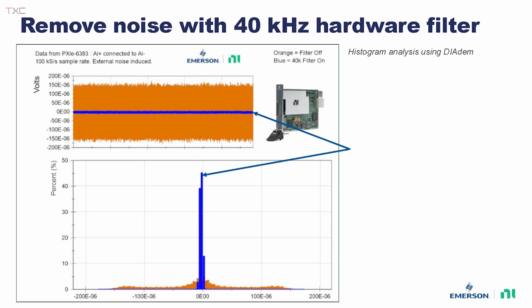What you're looking at in orange, this fuzz, is basically plus or minus 150 microvolts of noise that I was able to generate on that signal. That's with the filter off - so this is the 18-bit board, but the filter's off, and right now it's measuring a lot of noise.